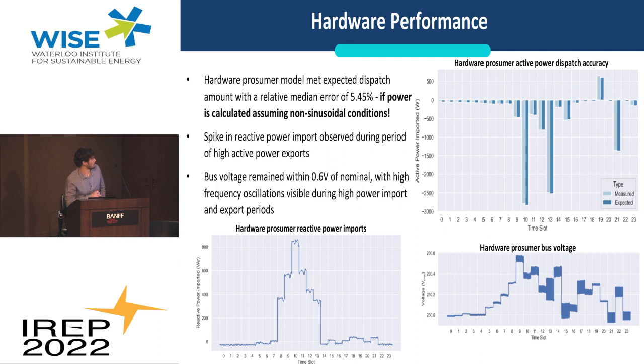Another interesting thing to observe is that we saw a big spike in reactive power import during periods when we were exporting lots of active power. Obviously this isn't ideal - we weren't intending to import reactive power when exporting to the grid to satisfy a market trade. This is interesting behavior produced by those commercial inverters, and we believe it was mostly caused by the PV inverter, the SMA Sunny Boy. This is something you'd have to take into account in real systems - this unintended reactive power import that isn't part of what you're trying to export to the market.